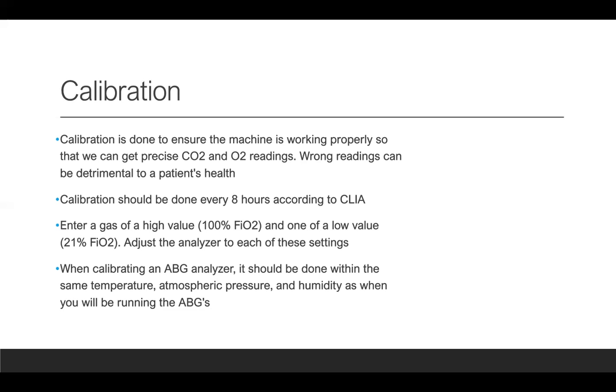When calibrating an ABG analyzer, it should be done within the same temperature, atmospheric pressure, and humidity as when you'll be running the ABG. So, for example, you don't want to be, not that you would, calibrating somewhere outside or somewhere with a different temperature compared to where you'll be running those, inside the emergency room or the ICU, wherever it might be.